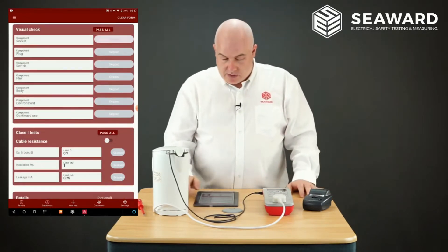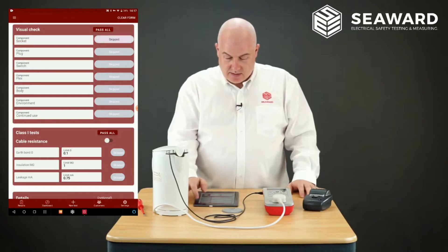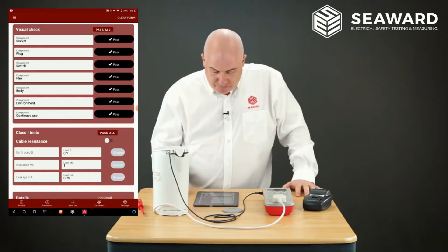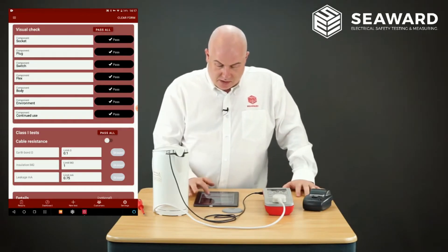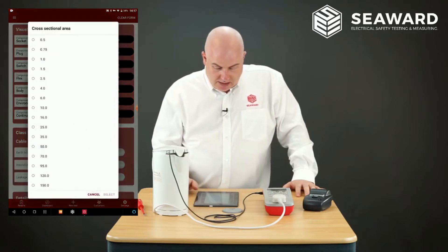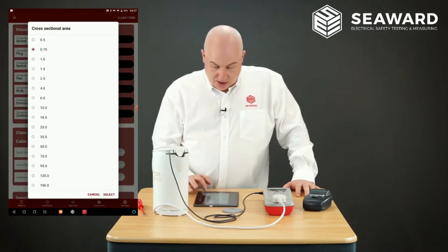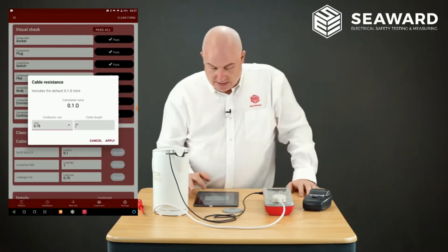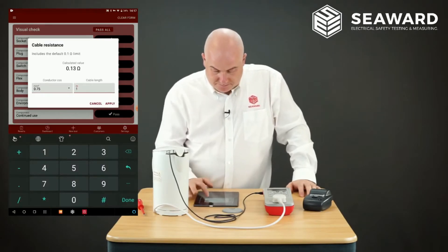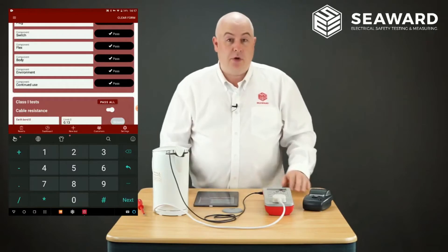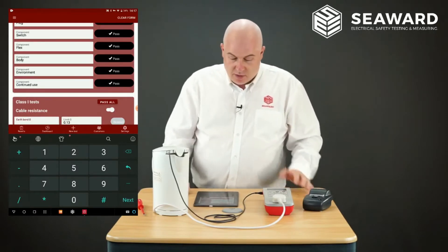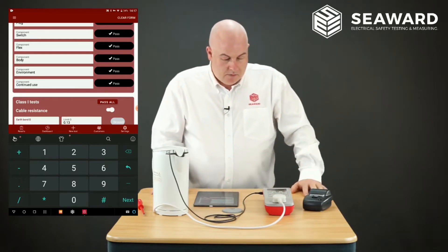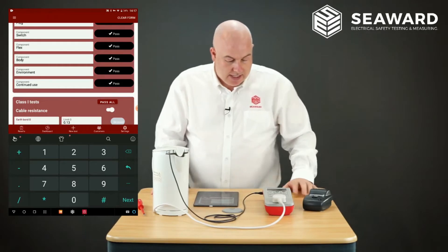It pops up to do the visual, so I can individually tick or cross the visual elements, but for speed I can do pass all because I know everything passed. For the electrical elements, I can use the lead resistance calculator. In this case I know this is a 0.75 cross-sectional area lead and approximately a metre long, so I'll put that in as a metre. That'll automatically work out the limit of 0.13. Now I'll do the test and the readings will come up on the Primetest, then I can enter those as I go.